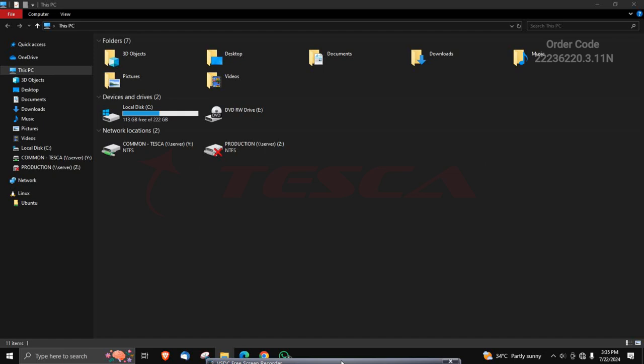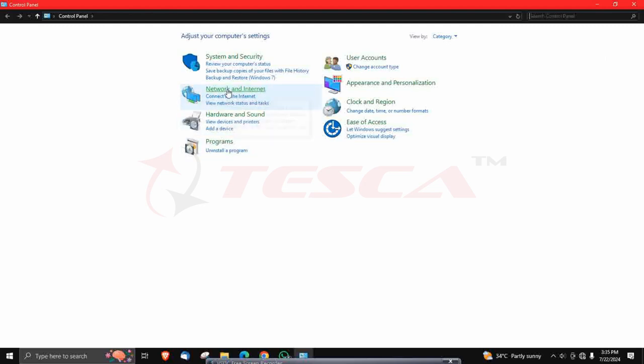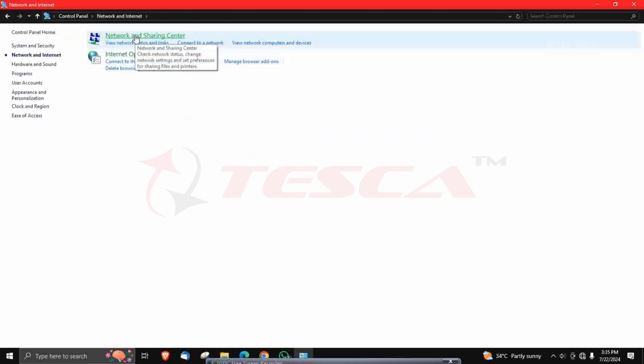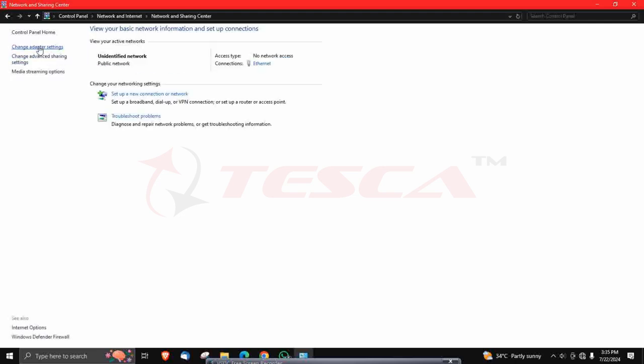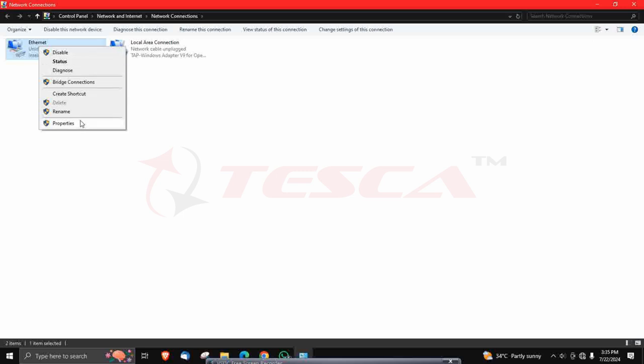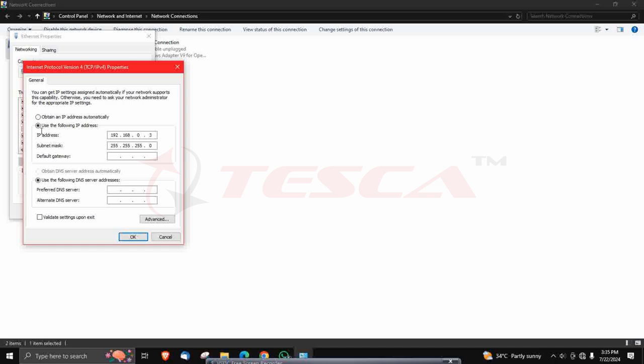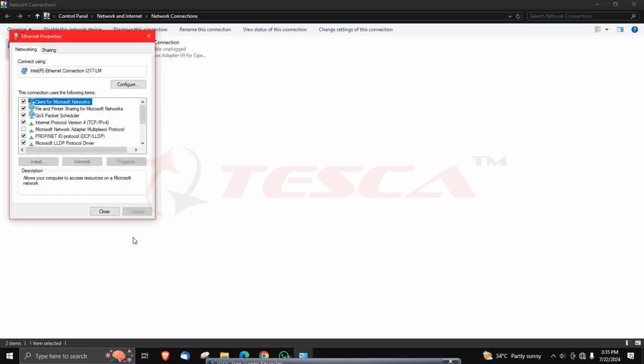Now we will deal with the software part of the networking of industrial controller. First of all, search for the control panel and open it. Then click on network and internet. After that, click on network and sharing center. Now click on change adapter settings. Now click on Ethernet and double click on it. Click on properties. Now click on internet protocol version 4 and check the properties. You can set the IP address. We have taken it as 192.168.0.3. Then click on use the following IP address. Now click on use the following DNS server address and after that click on OK.